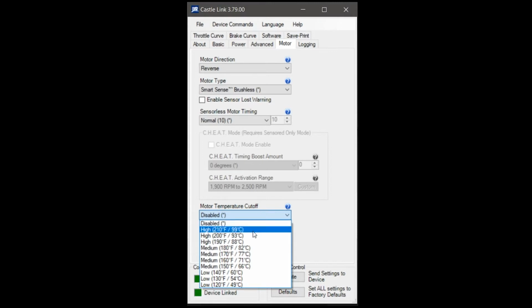So setting this at 210 degrees is a bit high for your speed controller. I would recommend something more like 180 or 170. Now keep in mind, if your sensor cable comes unplugged, your system will shut off. So that is a side effect that you'll have to deal with.